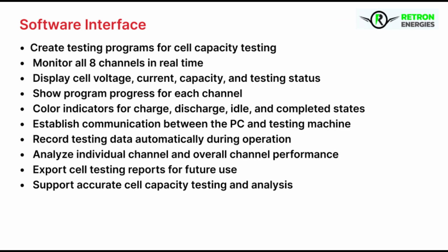In the previous video, we learned about the cells being placed correctly in the cell holders. Now we can move on to the software configuration and program creation process. The software used to control this machine is the cell testing application. This software allows us to create testing programs, monitor all channels in real time, record testing data, and export the final results after testing is completed.